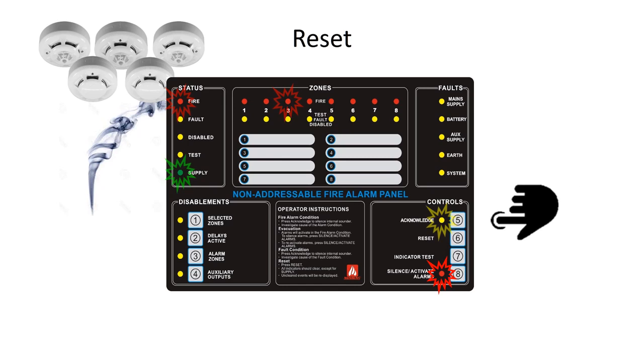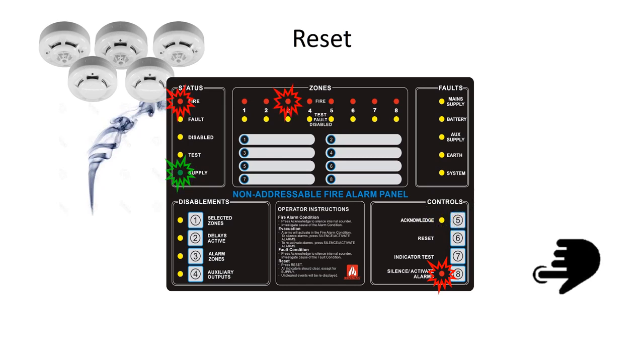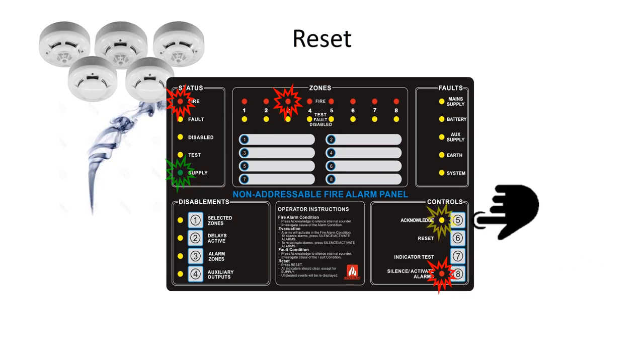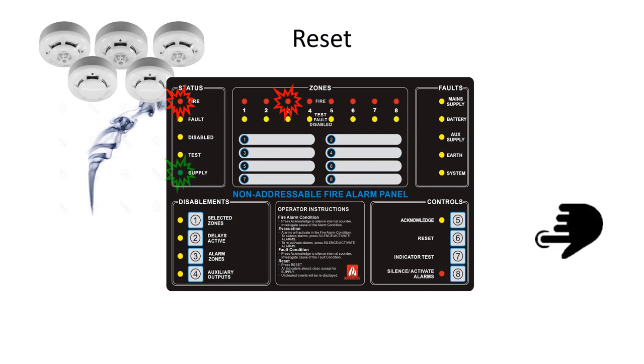Ensure all events have been acknowledged and the Acknowledge LED is off. Check that the Silence Activate Alarms LED is also off. Now press the Reset button and the Acknowledge button to confirm. Any unresolved events will cause the control panel to re-enter the alarm or fault conditions. Otherwise, the panel will just display the access level indication.